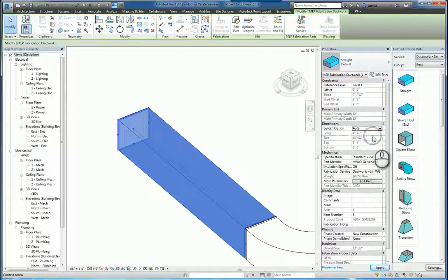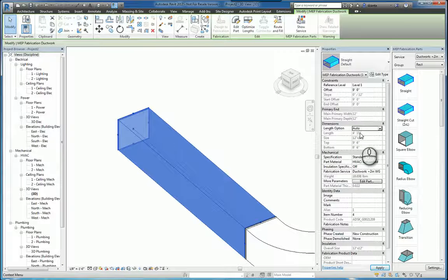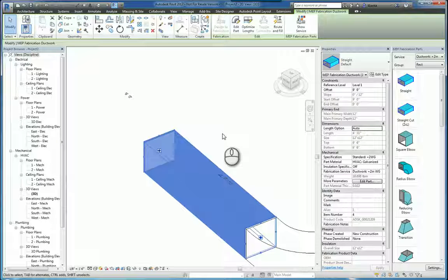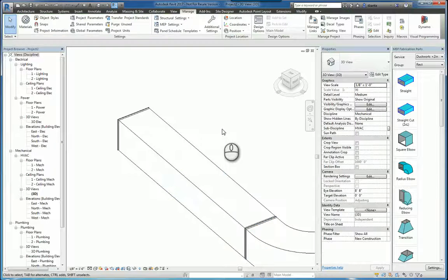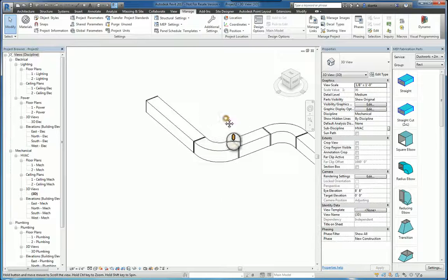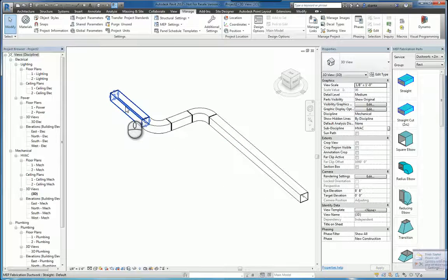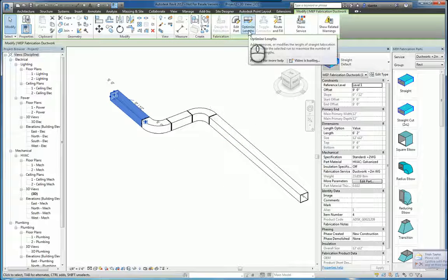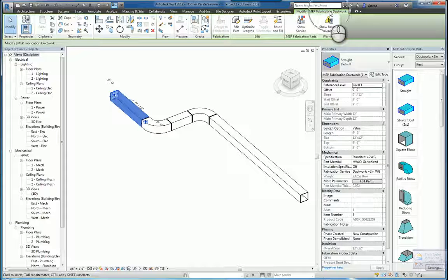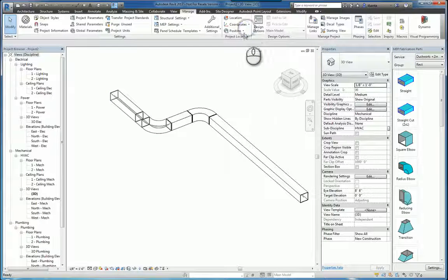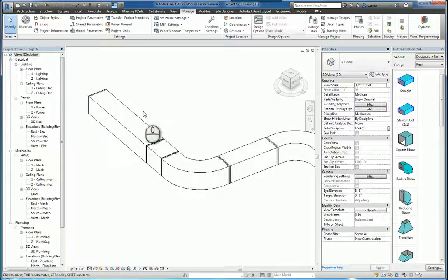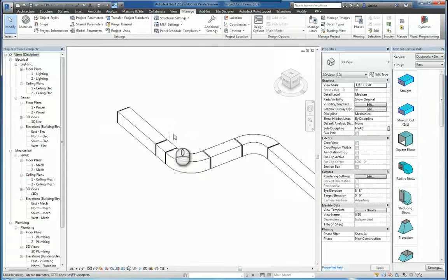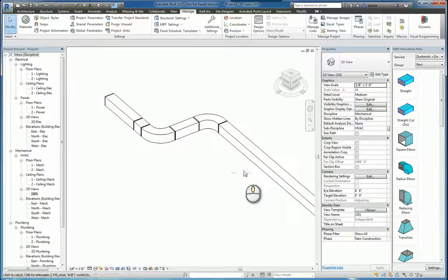If you switch it to auto, it's going to default to four foot eleven as the default and it would adjust accordingly. Now I'm going to undo that to hold it at that length. Now I can also select it and I can click optimize length in the modify MEP fabrication tab. So if I click optimize length, it'll put in that four foot eleven inch, really five foot long segment, and then put in a connecting piece that's remaining.